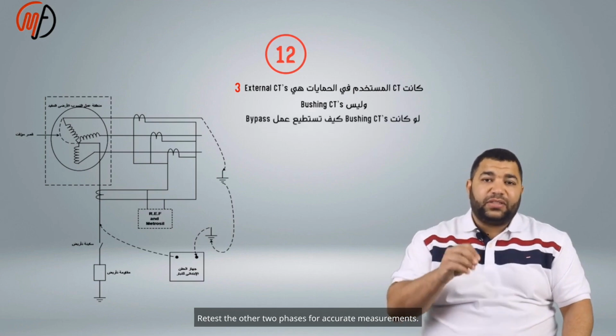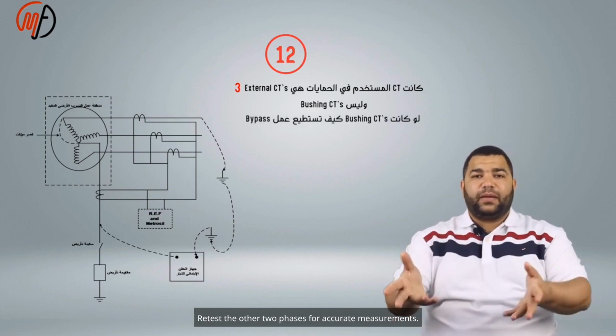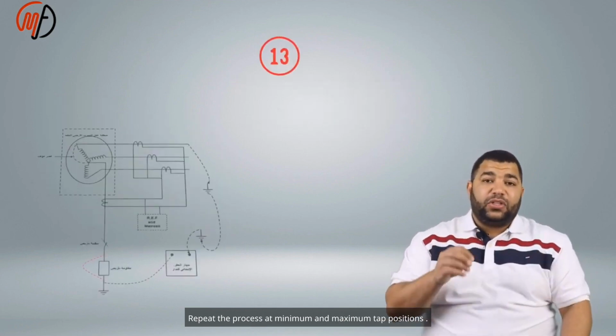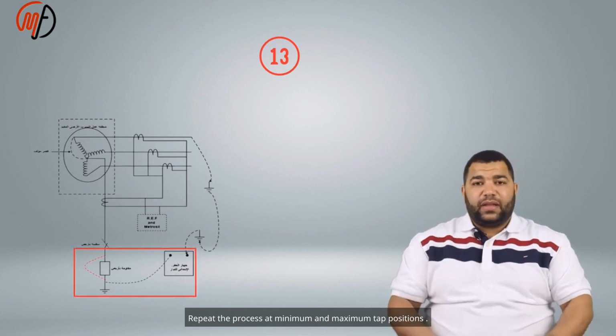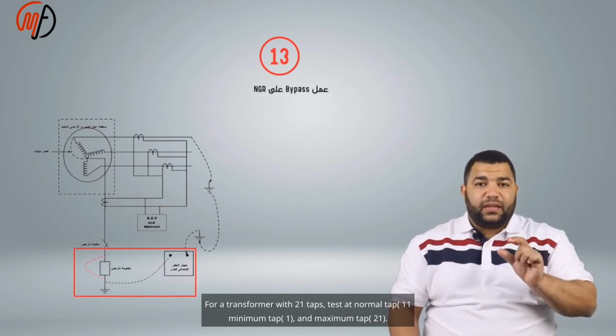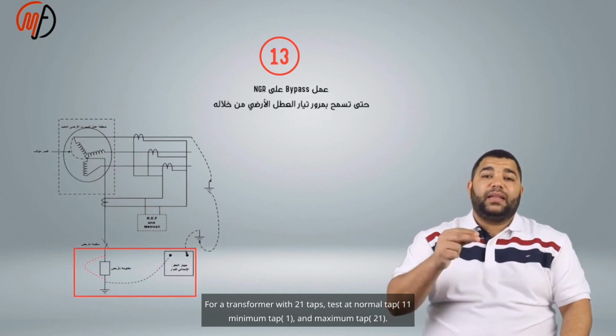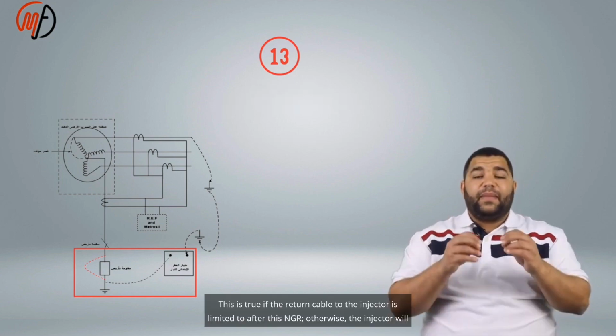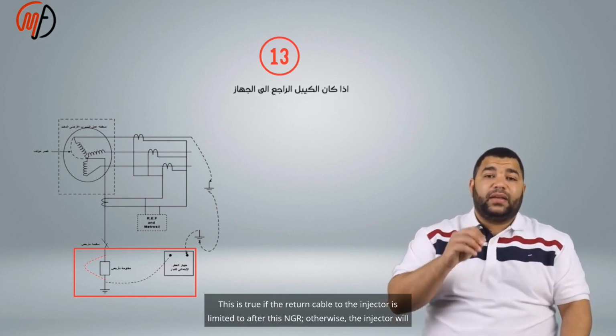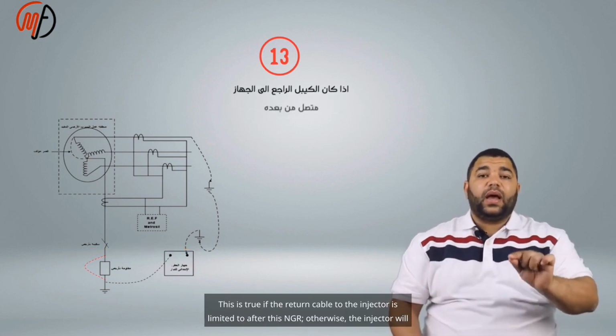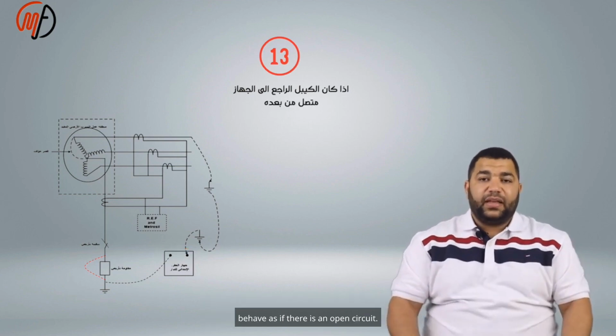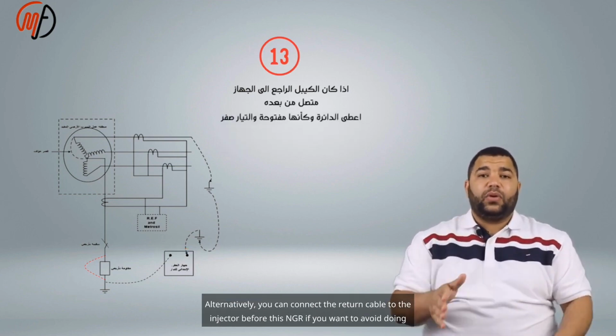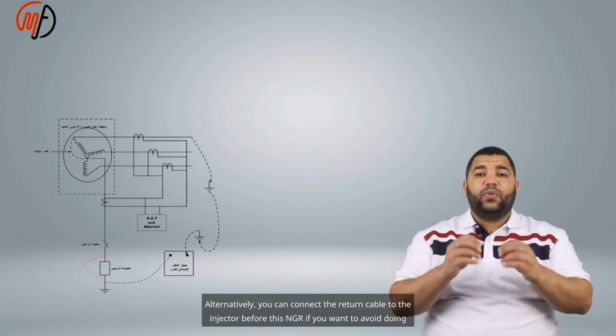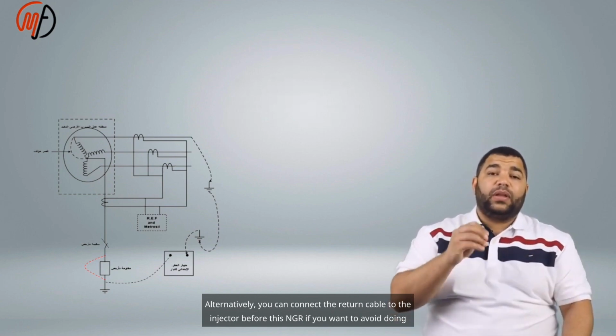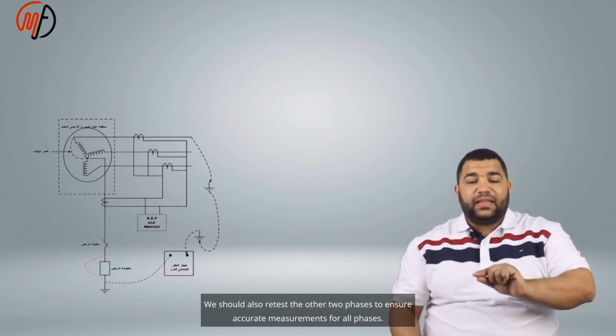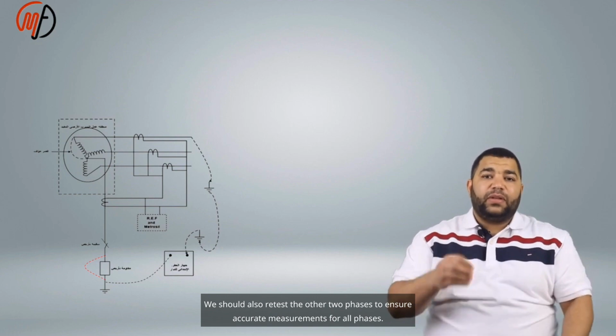Retest the other two phases for accurate measurements. Repeat the process at minimum and maximum tap positions. For a transformer with 21 taps, test at normal tap 11, minimum tap 1, and maximum tap 21. This is true if the return cable to the injector is limited to after this NGR, otherwise the injector will behave as if there is an open circuit. Alternatively, you can connect the return cable to the injector before this NGR if you want to avoid doing this bypass. We should also retest the other two phases to ensure accurate measurements for all phases.